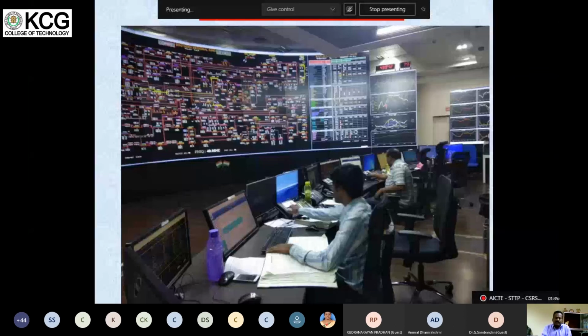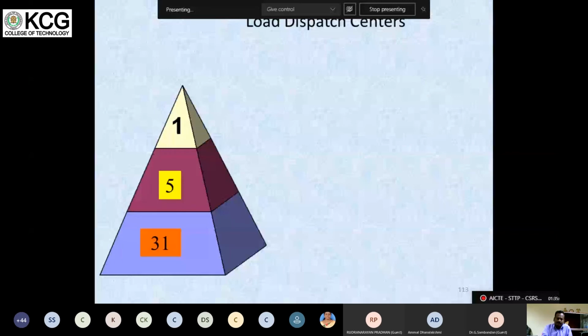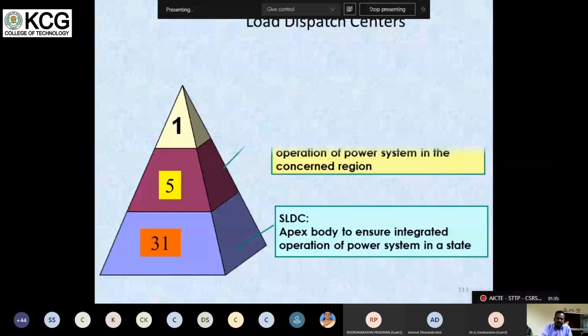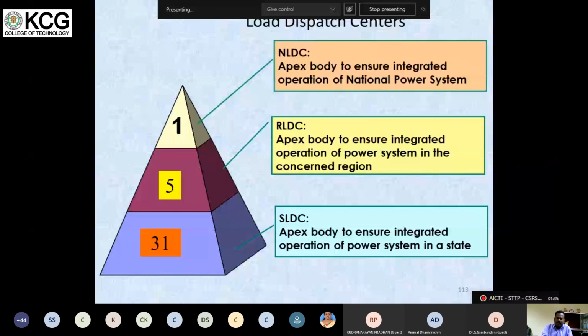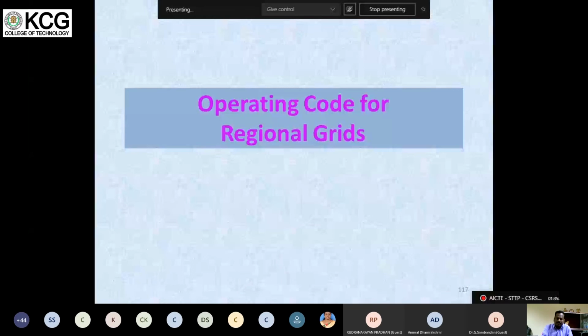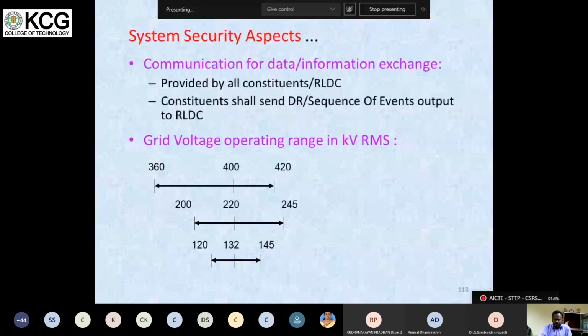So in India, we have SLDCs and we have 5 RLDCs and we have 1 NLDC, the National Load Dispatch Center. Under these 5 regional load dispatch centers, we have the SLDCs. Okay. This IEGC also specifies the voltage. For example, for a 400 kV system, the voltage should not go less than 360 kV and should not go more than 420 kV.